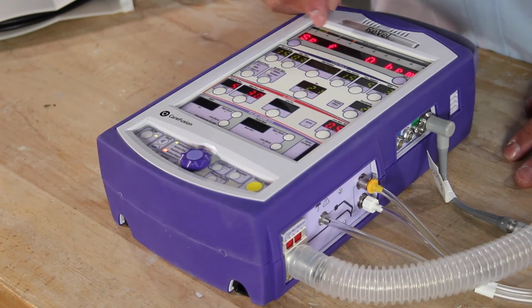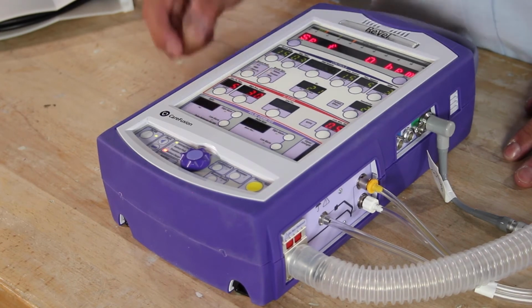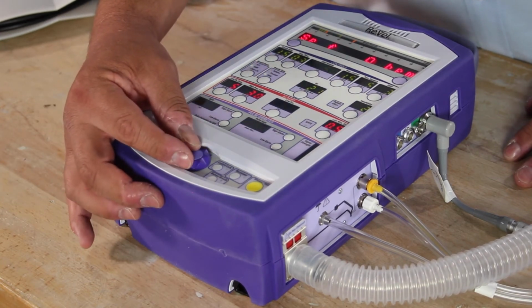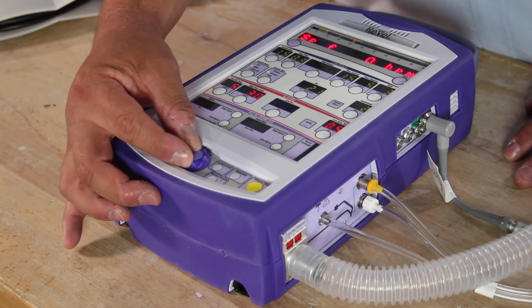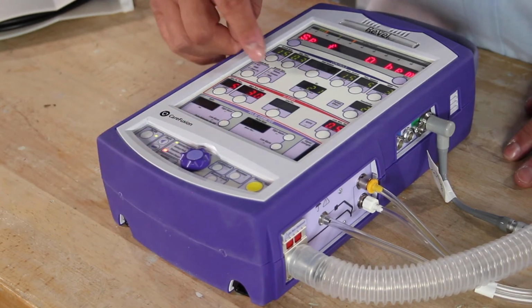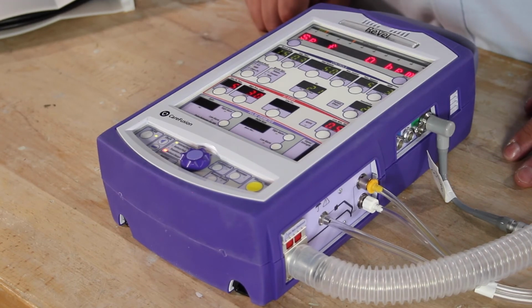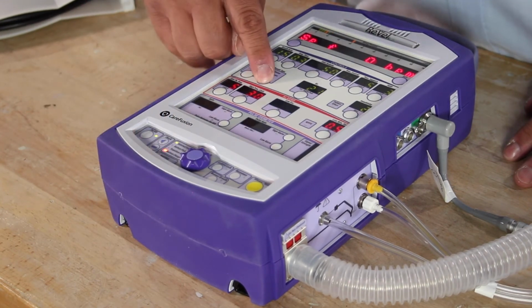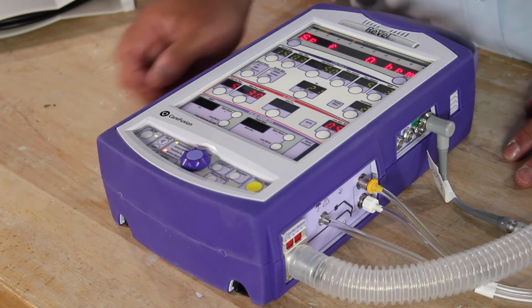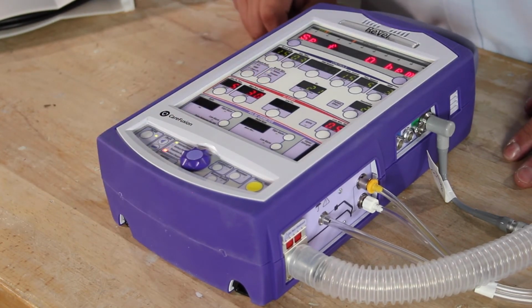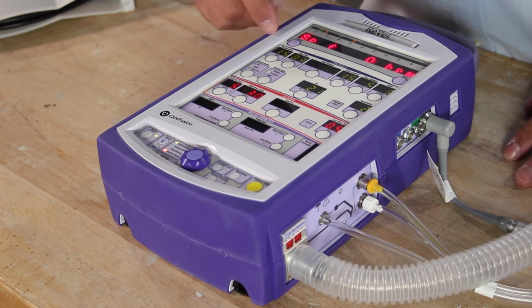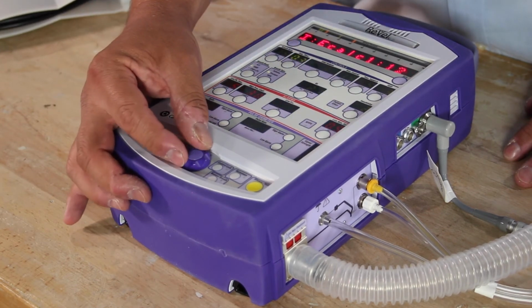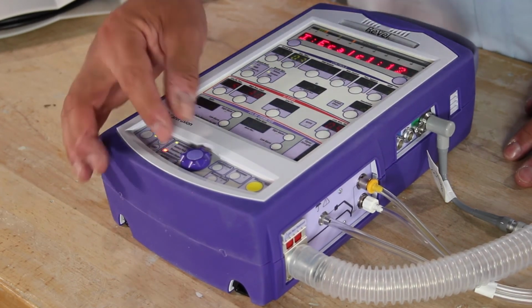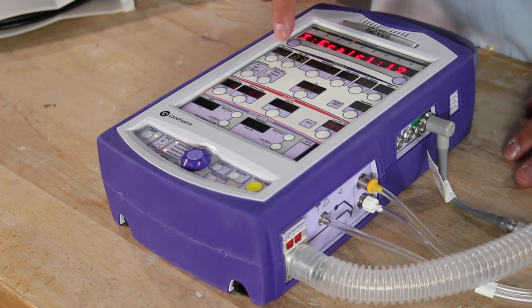Okay, let's go over here to breath type. Press, PRVC, pressure, volume. Okay, let's do that again. Press. Let's go back to pressure, hit select. Okay, let's go to I time. Let's make a change. Now, we're getting a blink. That's not allowing us to change. It's a limitation of the ventilator itself.